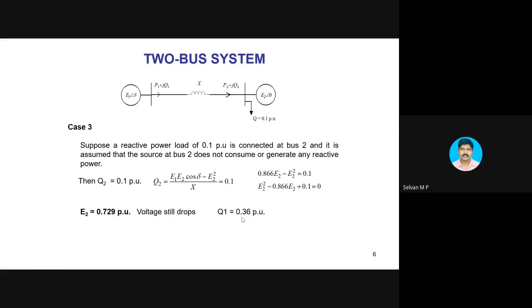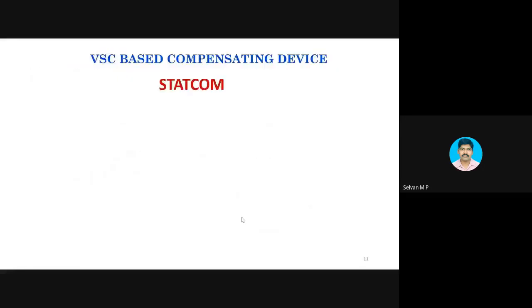So 2 points you have to think. In a system, if the reactive power flow is increasing, then voltage will drop. In other words, if I want to supply reactive power, I have to purposefully create a voltage difference. That's all you have to remember. So now I'll go to the STATCOM. So this is the voltage source inverter. This is the system. Now I want to supply reactive power into the system. Then I should have a voltage at the terminals of the VSC higher than this bus voltage. Then there will be a reactive power flow to the system.